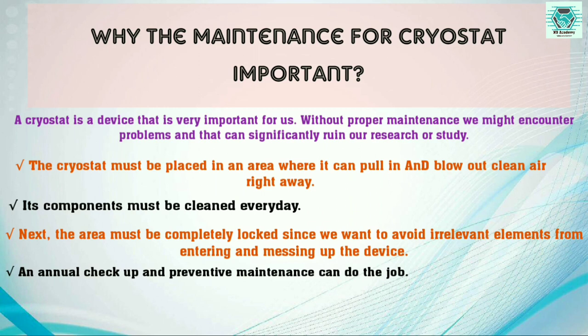Maintenance of the cryostat is important because without proper maintenance we might encounter different problems that can significantly affect our study. The cryostat must be placed in an area where it can pull in and blow out clean air. Its components must be cleaned every day. The area must be completely locked to avoid irrelevant elements from entering and damaging the device. An annual checkup and preventive maintenance should be carried out. Not only the cryostat, but every instrument in the lab must be maintained to get quick and easy results.